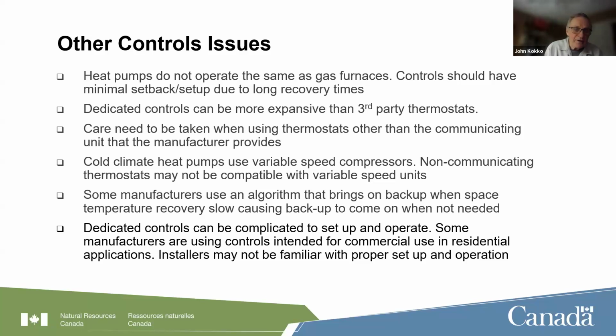Heat pumps can come with dedicated controls, or some heat pumps will accept third-party thermostats. The dedicated controls can be a little more expensive, but they can also be much more functional on the heat pump itself. One of the things that happens with heat pumps, especially cold climate heat pumps, is that they have variable speed compressors. Excuse me, non-communicating thermostats or third-party thermostats may not be compatible with variable speed. There's sometimes only a two-speed option for the compressor.